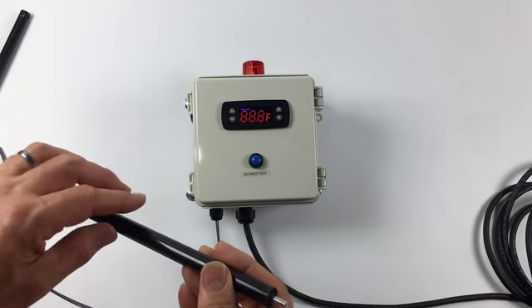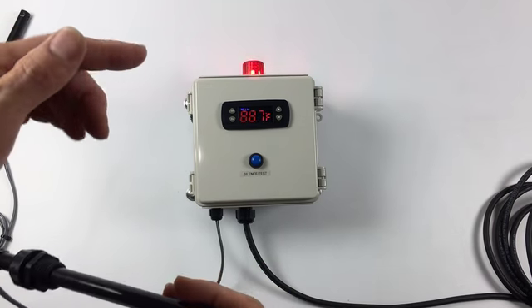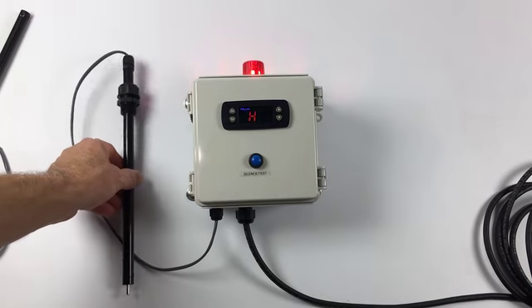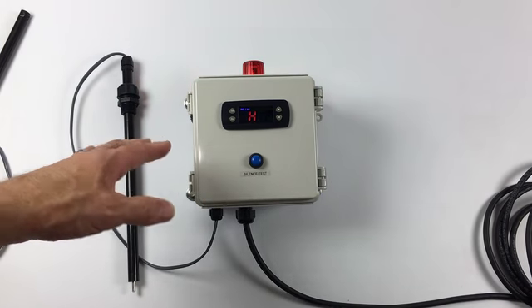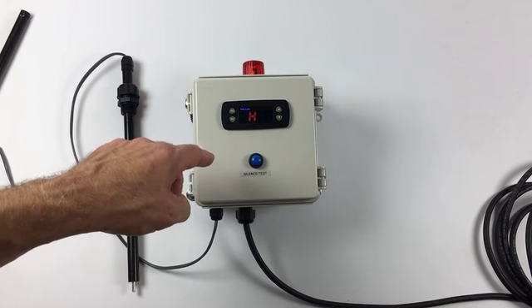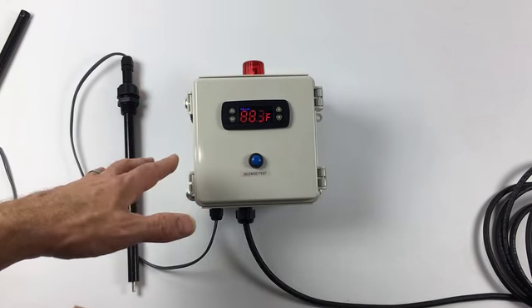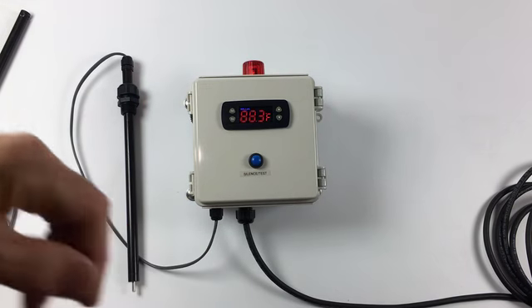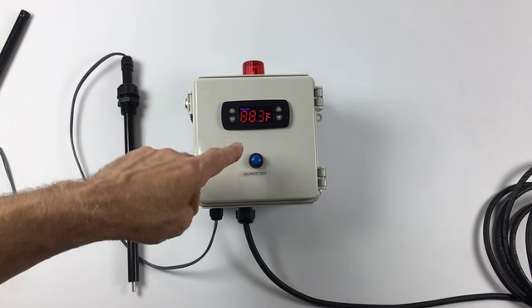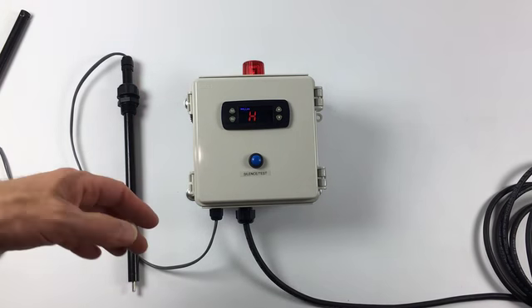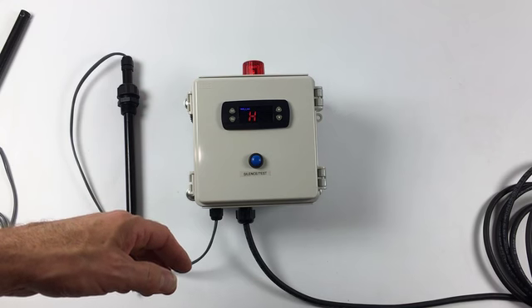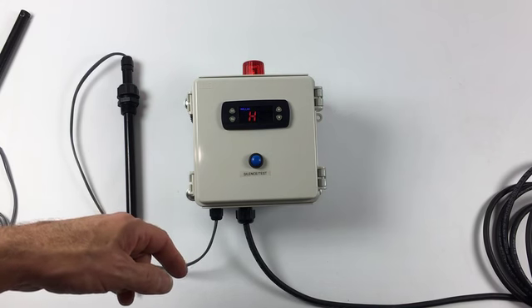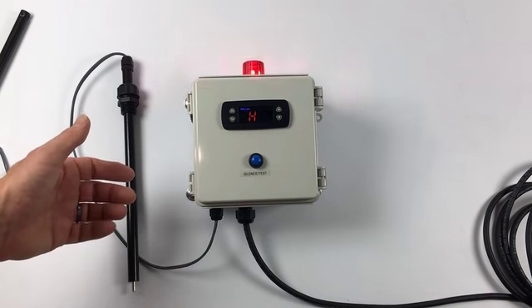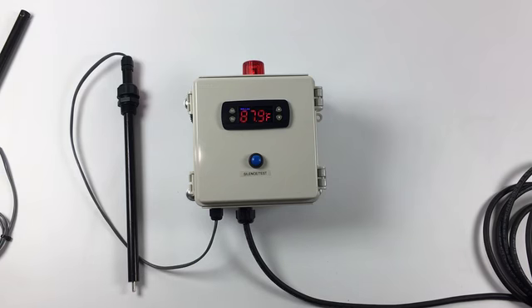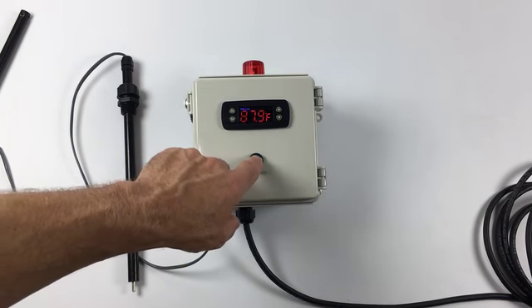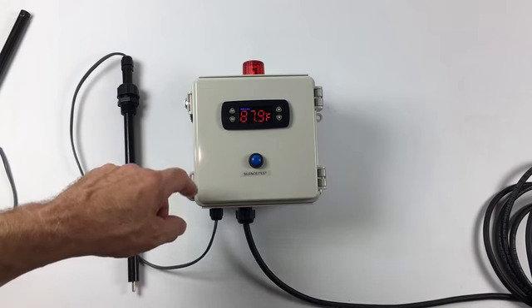The operator can silence it like so, but the flashing beacon won't go away until the process temperature reaches the set point within 2 degrees in this case. So here the temperature's declining, and when it gets back to 88 degrees, it'll be within range, and you'll stop seeing this high indication. And at that point, you'll be able to reset the flashing light. So here it's within the 2 degree window, so now I'm able to reset it and continue to operate normally.